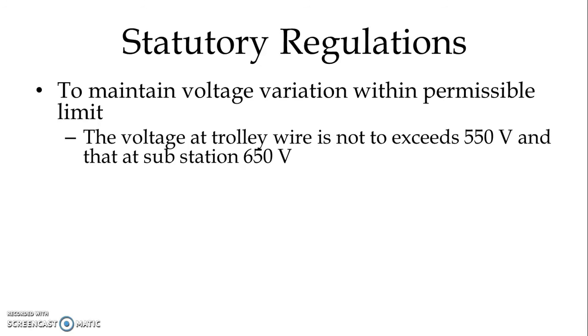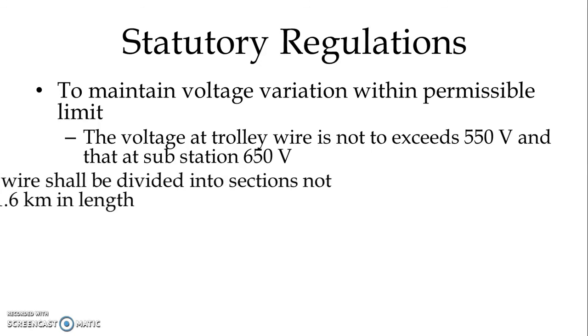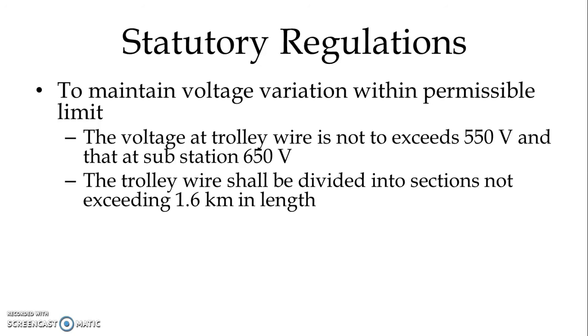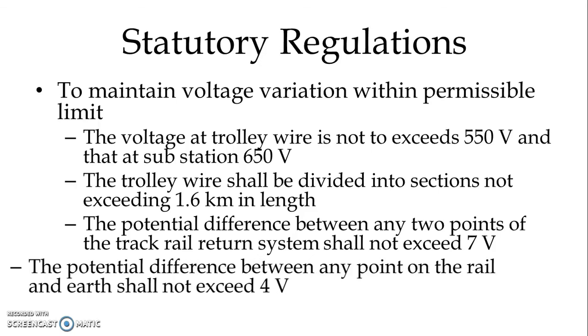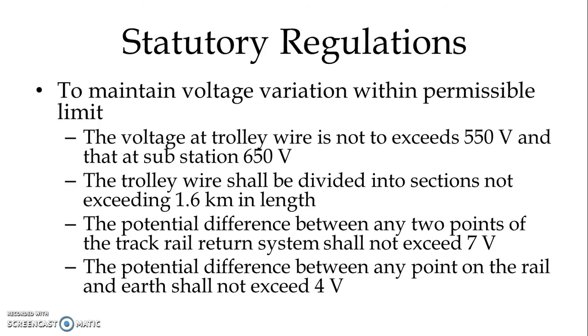We have to follow certain statutory regulations. The voltage at the trolley wire is not to exceed 550V and at the substation 650V. The trolley wire shall be divided into sections not exceeding 1.6 km in length. The potential difference between any two points of the tracked rail return system shall not exceed 7V. By observing these regulations, we can maintain the voltage variation within a permissible limit.